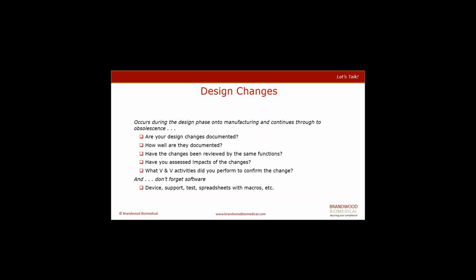And most importantly, don't forget software. Not just in the sense of a device, but support software, test software, spreadsheets with macros, and other forms of software. These will and do form part of design changes.